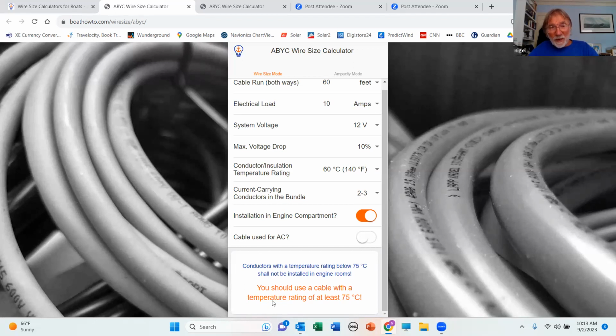And now look what we got. We got a little pop-up here that said you should use a cable with a temperature rating of at least 75 degrees centigrade. That's because we clicked the high ambient temperature, and the standards assume that the ambient temperature in an engine room is 50 C in the States or 60 C in Europe, which means we've preheated that conductor to the point at which we're not allowed to put any amps through it. So we're going to have to go back in here and raise the temperature on the insulation. We're going to have to get a higher quality conductor. And if we go to the next one up, 75 C, we discover we need a 12 gauge conductor. And this is determined by voltage drop requirements, which exceed those of ampacity.